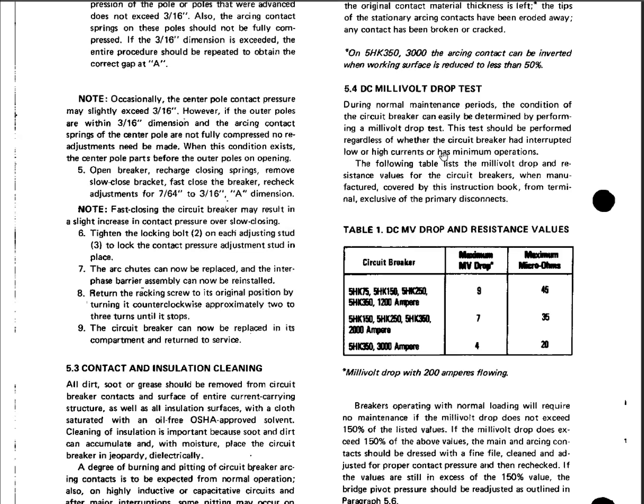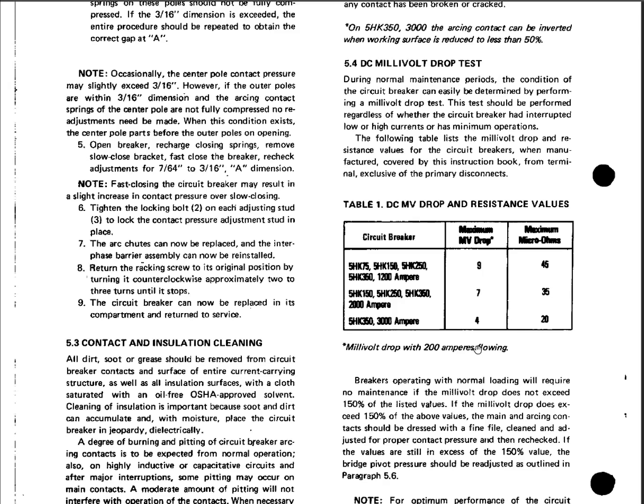It says that in order to perform this millivolt drop check, what you have to do is apply 200 amps. It doesn't tell you to perform this check with 1200 amps, it tells you 200 amps, and this is what you should get. You can perform this a whole bunch of different ways, and you can say I'm going to do it with 50 amps because that's the only one I have. Well then you could use the 45 micro ohm.